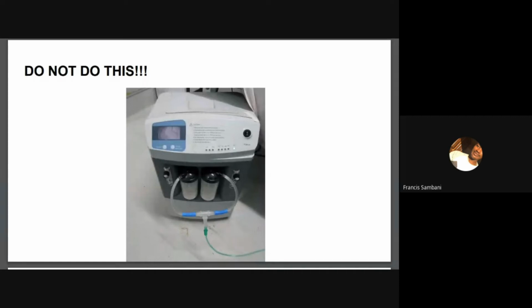The recommendation is that, to prevent this misuse of oxygen concentrators with dual flow meters, frequent user trainings are required so that the users are aware that they're not supposed to do this. Mostly these concentrators come with 2 flow meters because they might be used on another patient. Let's say you want 5 liters on one patient and 5 liters on another, but your concentrator is a 10-liter output. That's why they do it, but not necessarily that you should open both flow meters to the maximum flow. No.